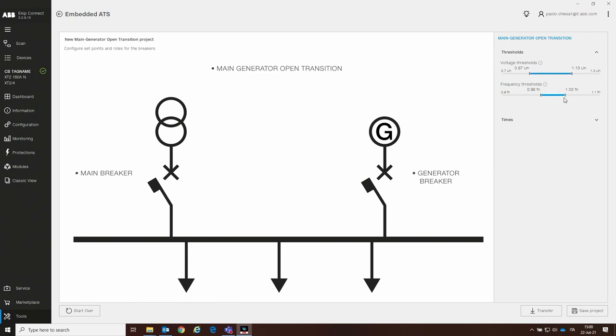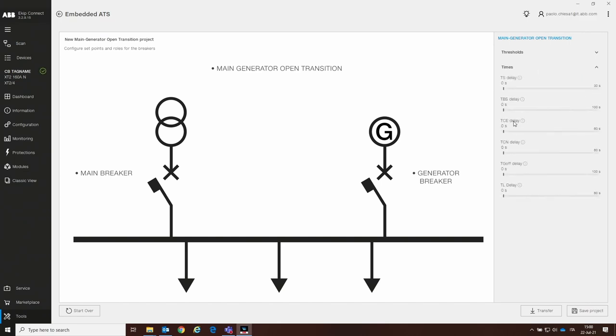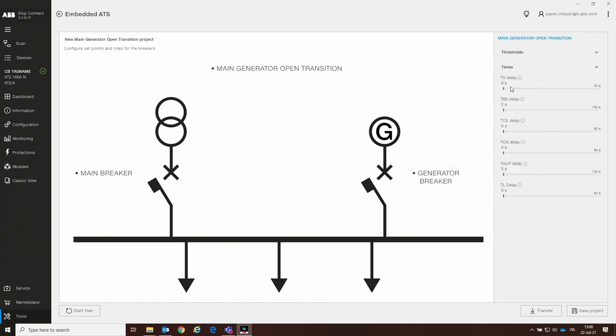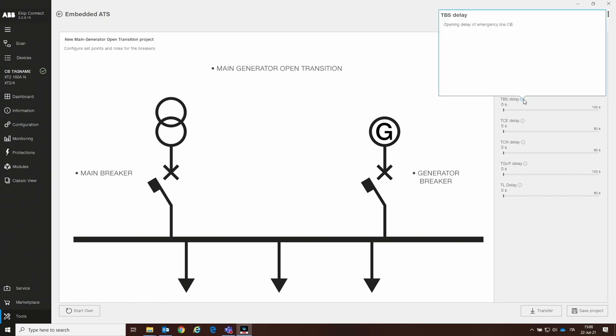The threshold settings depend on customer needs. We also need to set all the times related to the automatic transfer switch — times related to the generator start, the opening time when a fault is recognized on one of the two sources, and so on. All details about these settings are shown when you click on the information button. For example, the TS delay is the generator start delay after detection of a fault in the mains — the timing you want before the generator starts when a fault occurs on the mains. In this case I want two seconds.